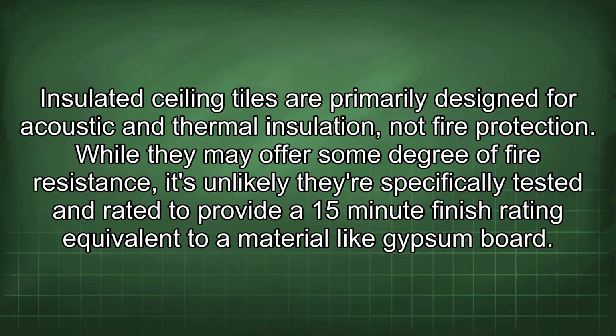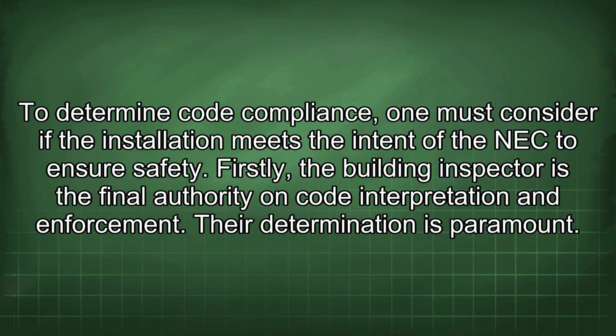Insulated ceiling tiles are primarily designed for acoustic and thermal insulation, not fire protection. While they may offer some degree of fire resistance, it's unlikely they are specifically tested and rated to provide a 15-minute finish rating equivalent to a material like gypsum board. To determine code compliance, one must consider if the installation meets the intent of the NEC to ensure safety.